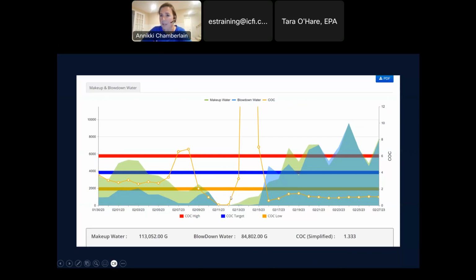And then after that, the service provider came. So something happened in here. Then I'm really low, running down below 1. What else do I notice? My makeup water and my blowdown water are basically equal. So my first thought is, oh, their blowdown valve is stuck open. It's just running single pass. But let's dive into the high resolution 1-minute data and see, let our fingers do the walking.